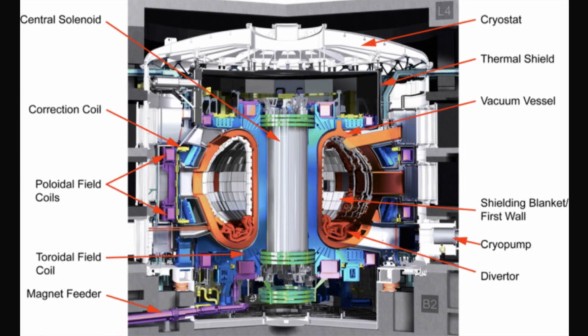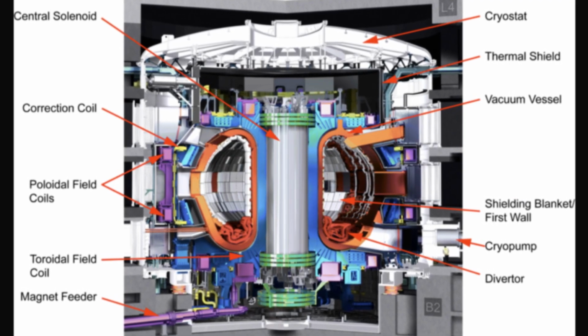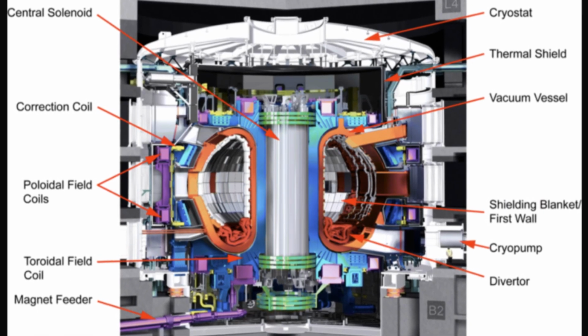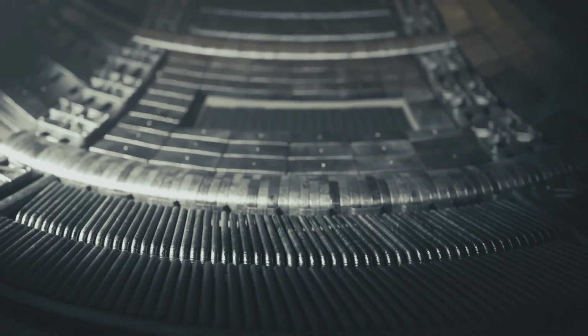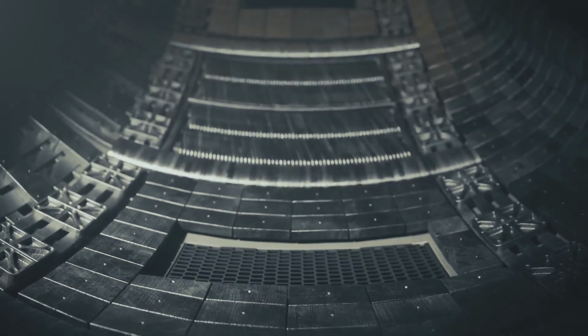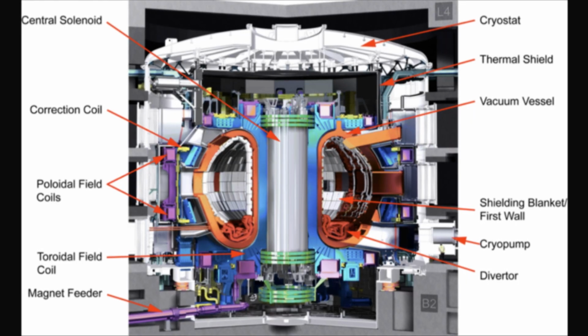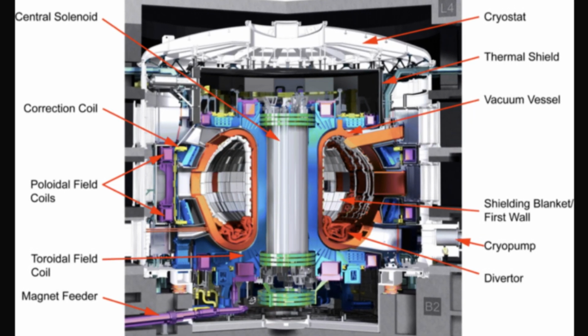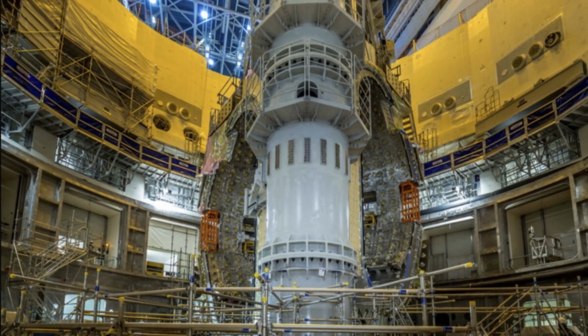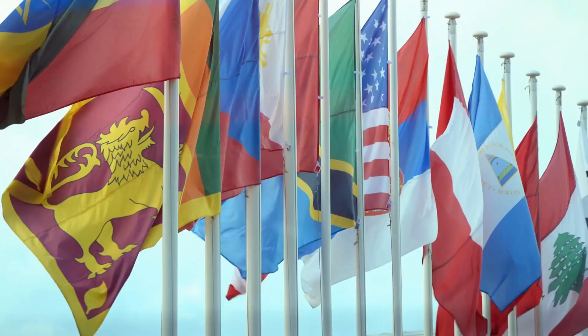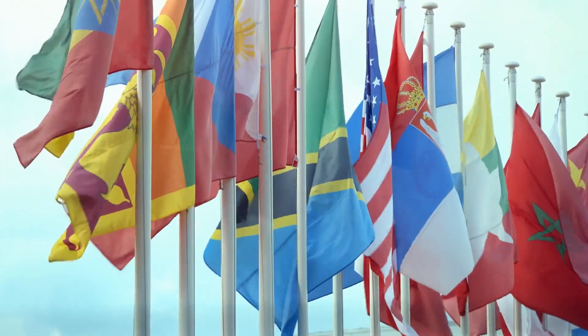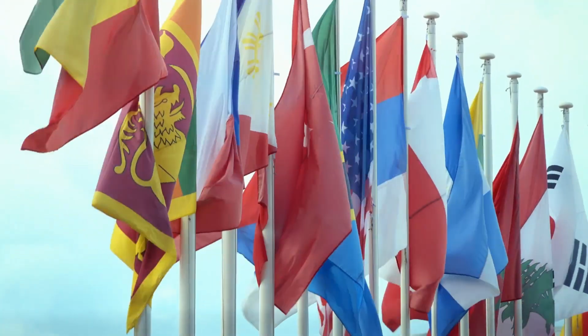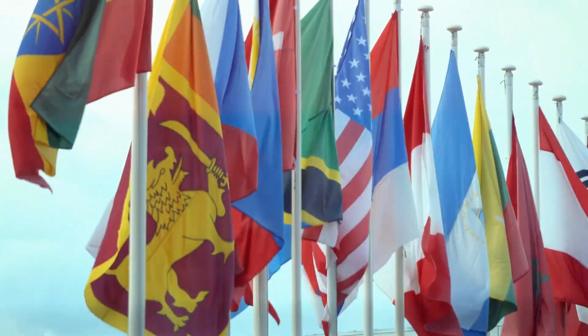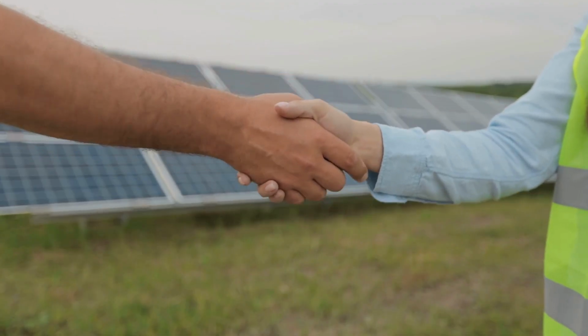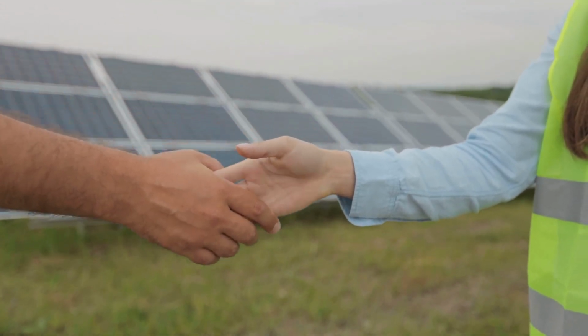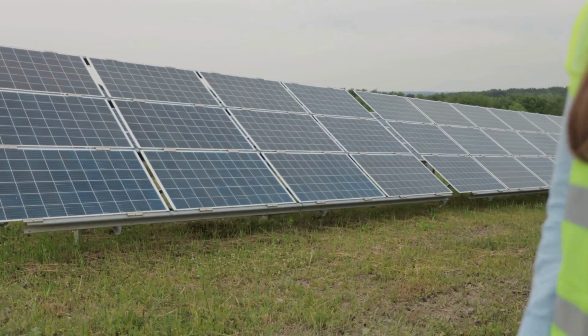The tungsten divertor tiles are designed with intricate engineering to handle extreme heat loads. These tungsten tiles are bonded to a copper alloy heatsink that is actively cooled by pressurized water flowing through it at high speed. ITER is not just a scientific marvel, it is one of the most ambitious and complex international collaborations ever conceived. One partner calls it a global scientific partnership of unprecedented scale.